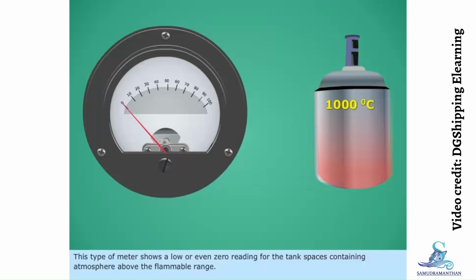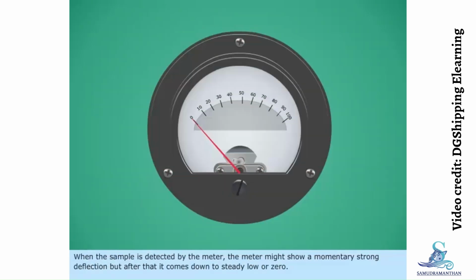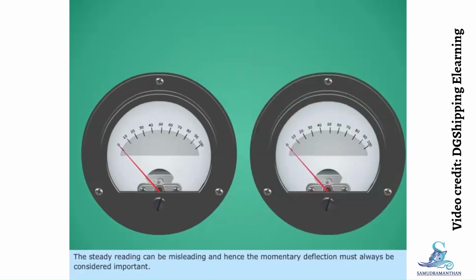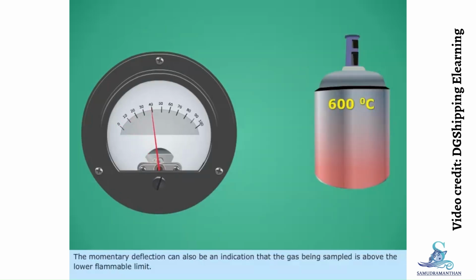This type of meter shows a low or even zero reading for tank spaces containing an atmosphere above the flammable range. When the sample is detected, the meter might show a momentary strong deflection, but after that it comes down to steady, low or zero. The steady reading can be misleading, and hence the momentary deflection must always be considered important. The momentary deflection can also be an indication that the gas being sampled is above the lower flammable limit.